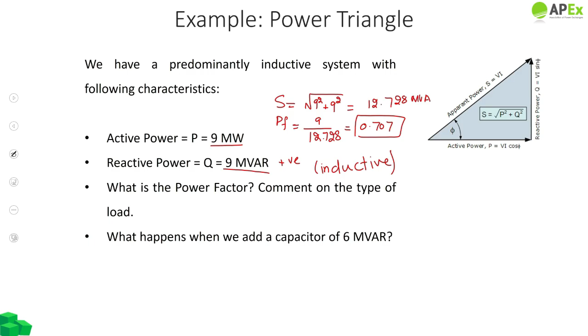So to improve the power factor of an otherwise predominantly inductive load, we would add a capacitor, and in this case we added a capacitor of 6 MVAR. Our Q new would become what Q was previously before applying capacitors, which is 9, and then we added a capacitor of 6 MVAR, which means 6 MVAR is being supplied to the system. So essentially this becomes minus 6, since it's being supplied as opposed to consumed. This becomes 9 minus 6 equals 3.